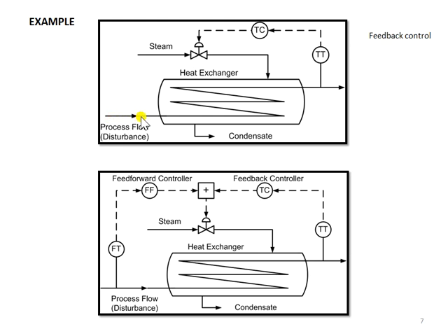This is definitely a problem, because if the temperature has been well regulated, let's say the temperature has already achieved a certain steady state value and is following the set value, but the process flow rate suddenly increases, the whole process will be upset and the temperature output of the heat exchanger will drop.